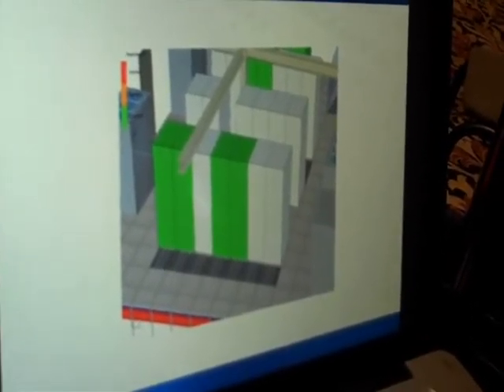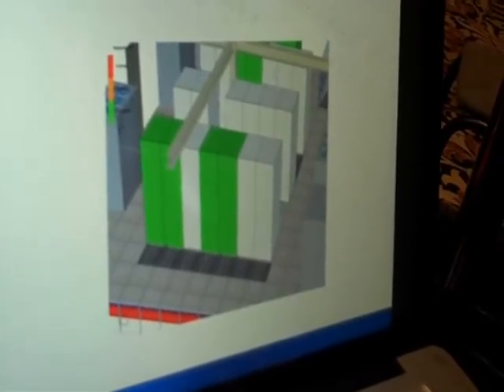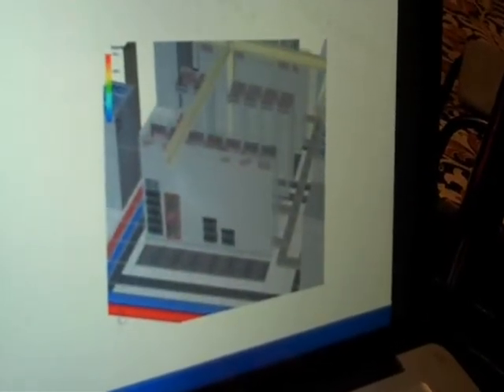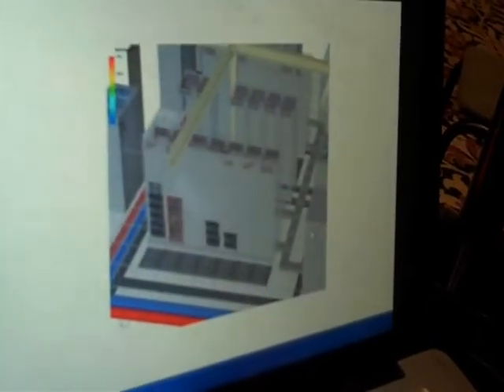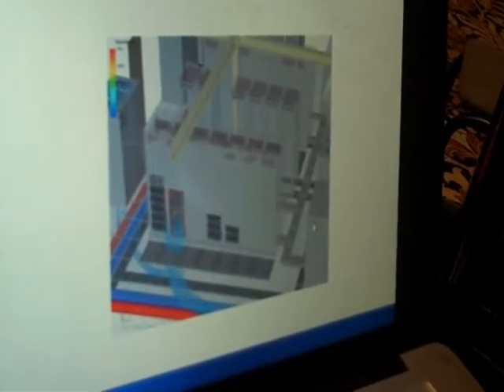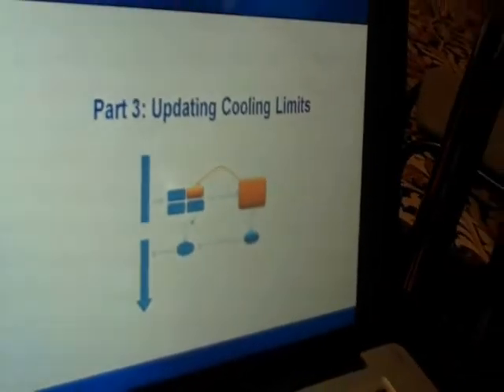At this point, engineering can say go ahead and install it. You're past cooling limits, but it doesn't harm anything else in the area. For engineering purposes, they can also see the resulting airflow, because the CFD simulation is run and they can use this to verify. We know that in that cabinet, we can actually handle a little more load than before. But your room capacity hasn't changed, so at this point you can update the cooling limits based on the changes that you've made in the data center.